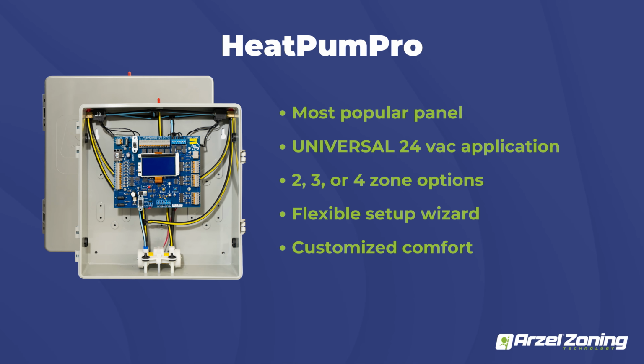The next panel that we have here is going to be our HeatPumPro panel. And this is pretty much our most versatile panel. It's usually the panel that I recommend any contractor to go with. It'll work for any 24-volt system on the market as it ships. You don't need any external components. Even if it's a dual fuel system, you can handle all that staging with just single stage conventional thermostats.